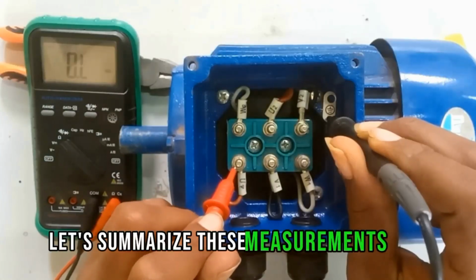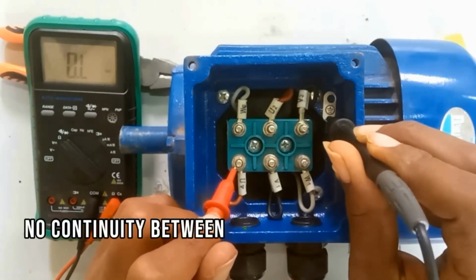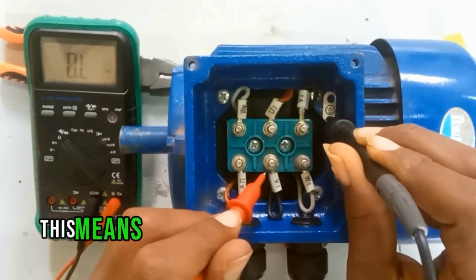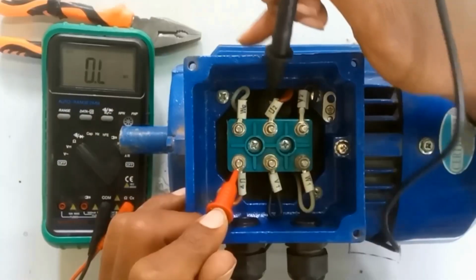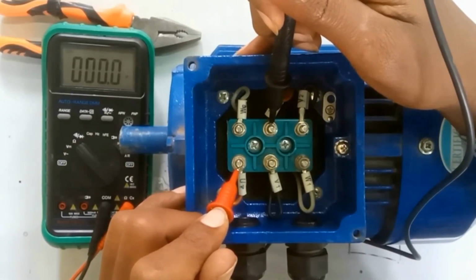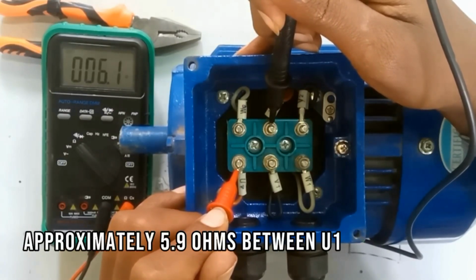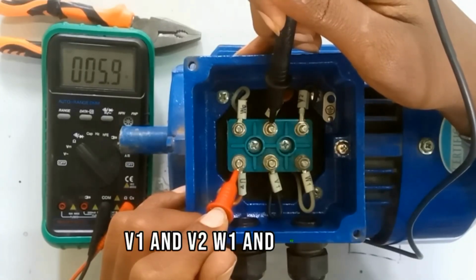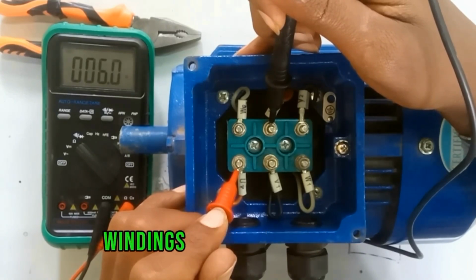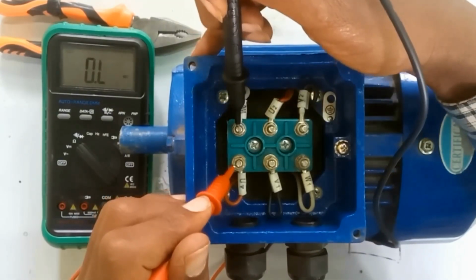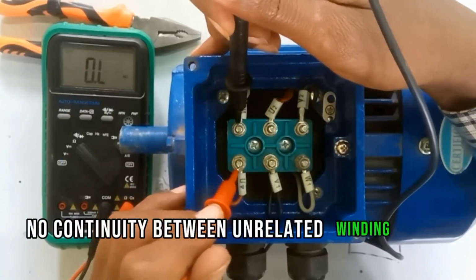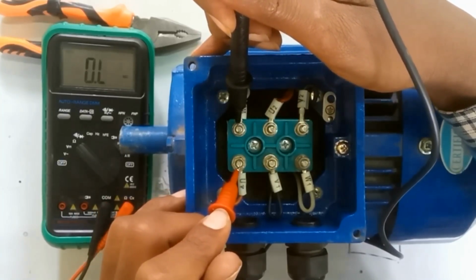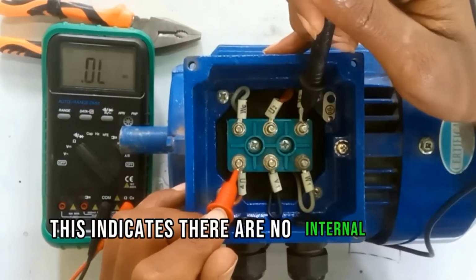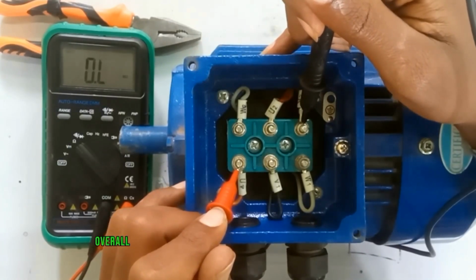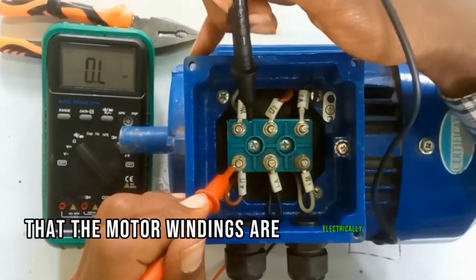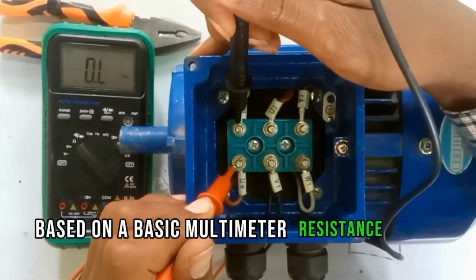Let's summarize today's measurements. No continuity between the motor body and any winding. This means the insulation to ground is good. Approximately 5.9 ohms between U1 and U2, V1 and V2, W1 and W2. This confirms that all 3 windings are continuous. No continuity between unrelated winding terminals. This indicates there are no internal short circuits between the different phases. Overall, this result suggests that the motor windings are electrically healthy based on a basic multimeter resistance test.